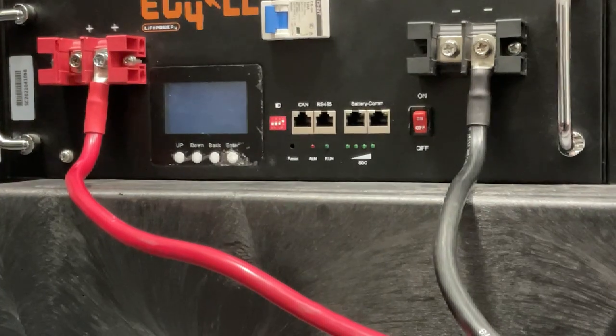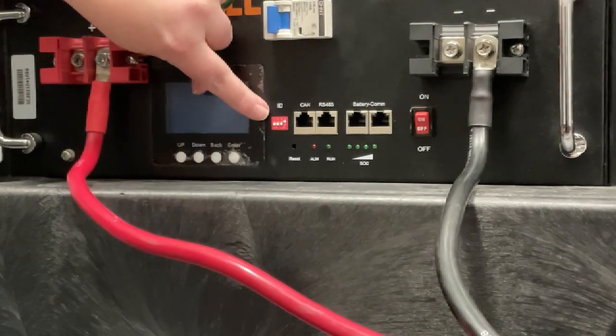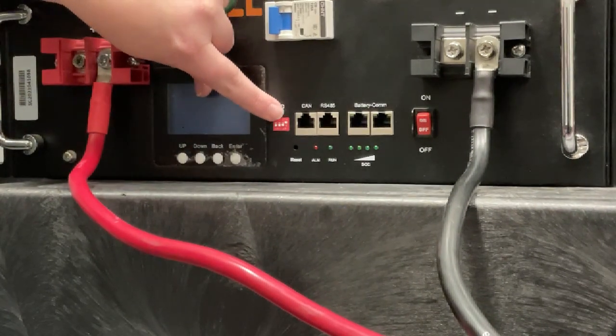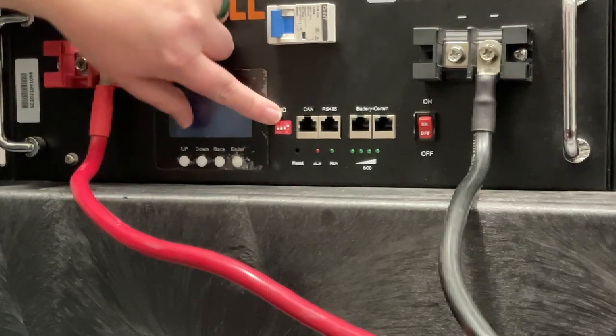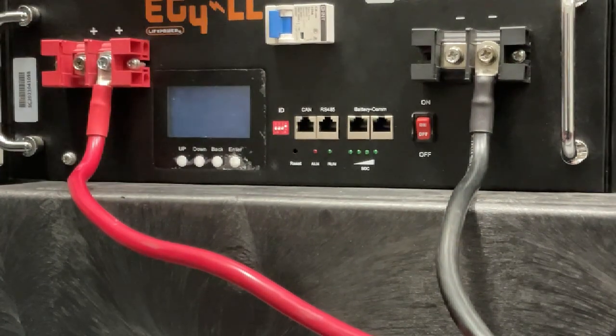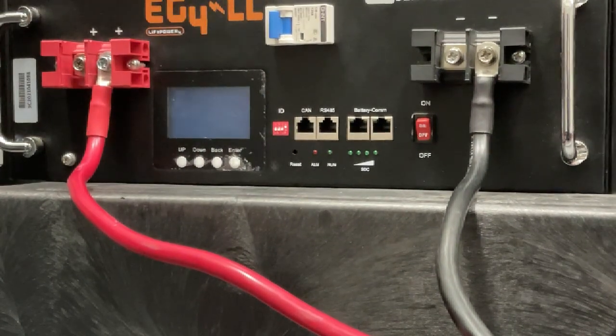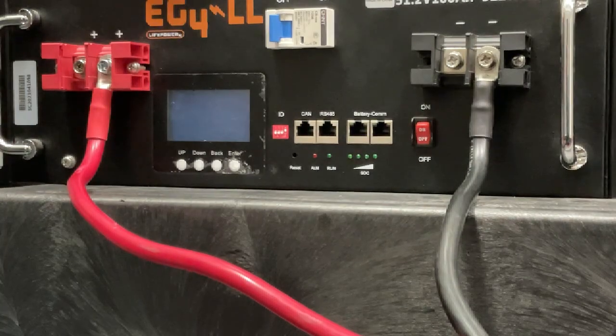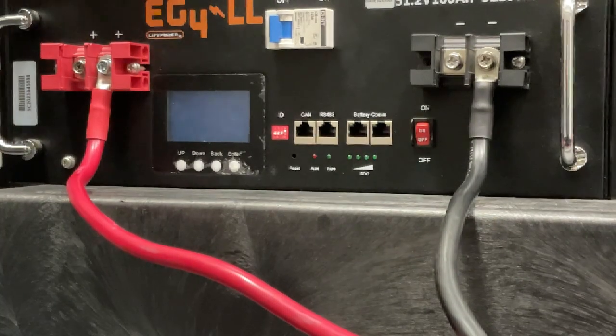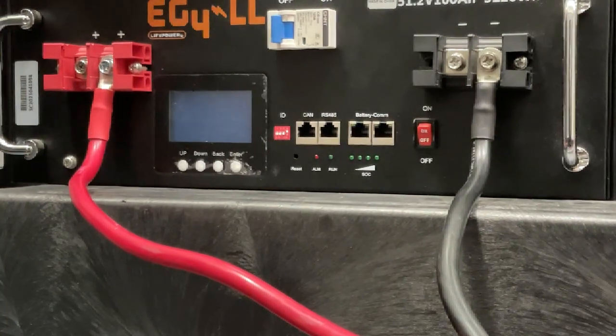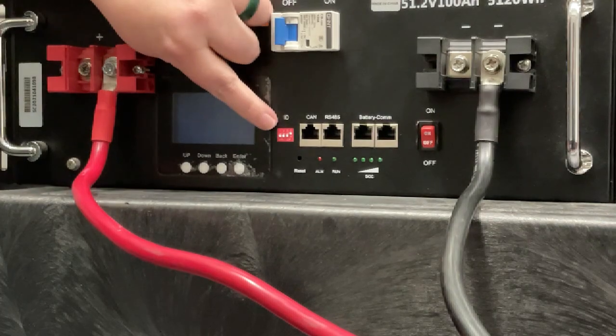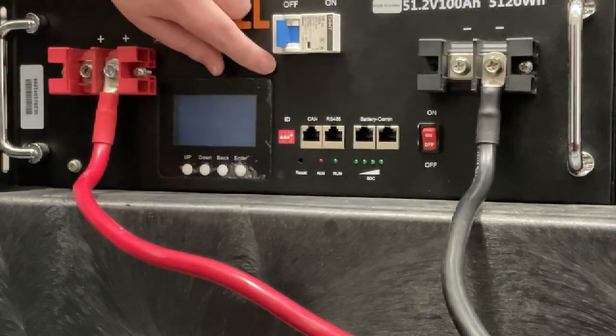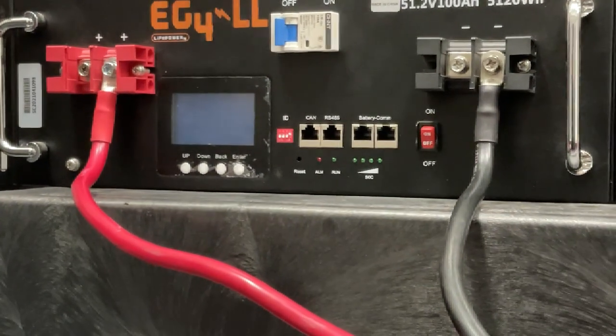...would need to be in the down, down, down, up position. As we mentioned before, every other battery after that can have any dip switch configuration you would like so long as no two batteries are the same and so long as no other battery has this down, down, down, up configuration other than your master.